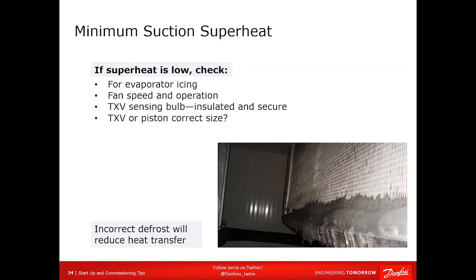So you got low superheat. What do you check? Well, first thing, my favorite is evaporator icing. So if you're in a refrigeration system and you have ice, in this case here, that tells me that there was not enough drip time to get rid of the condensate, or your condensate drain was full. Take your pick. Another one means if you're covered in ice, you don't have enough defrost. So if you have a defrost timer, it was probably set for the winter time. And in the summertime, the air contains a lot more moisture. You need far more frequent defrosting. Better yet, throw an electronic control and do defrost on demand. It will get rid of this problem.